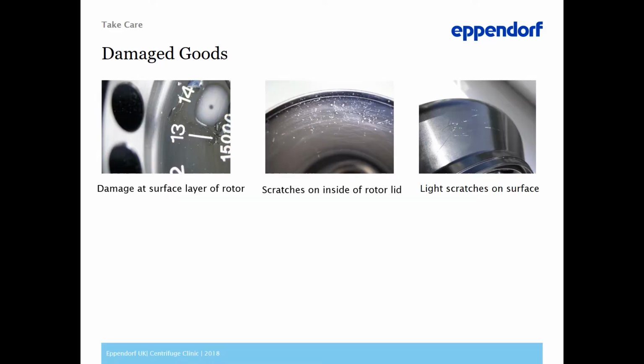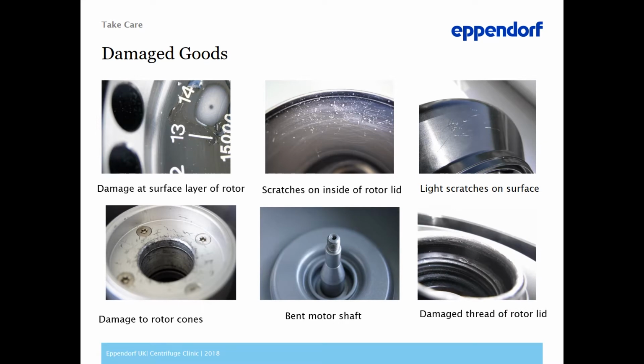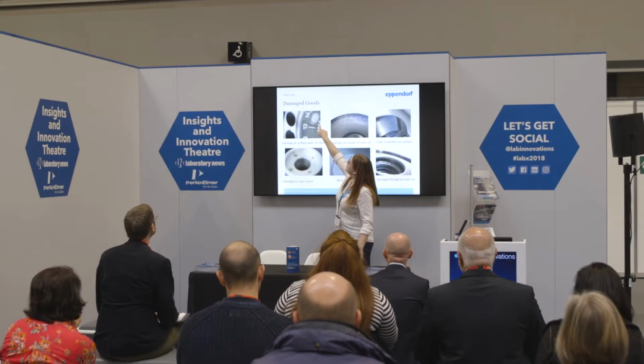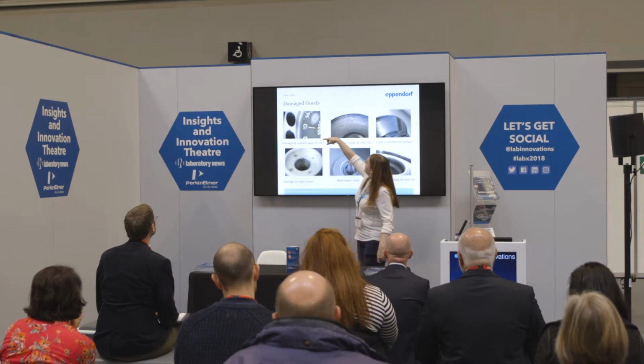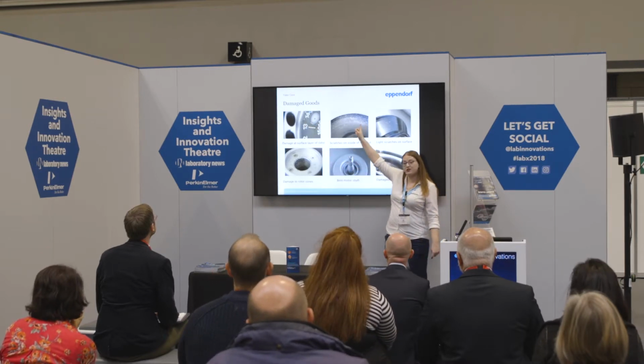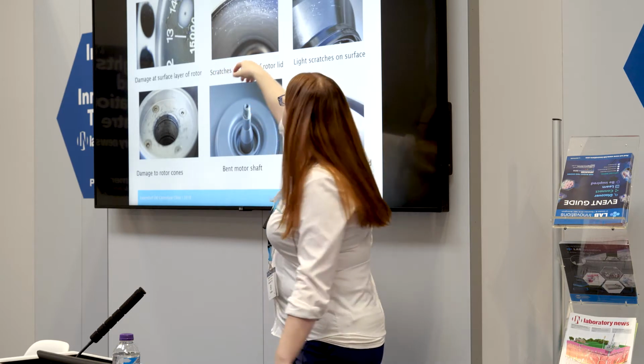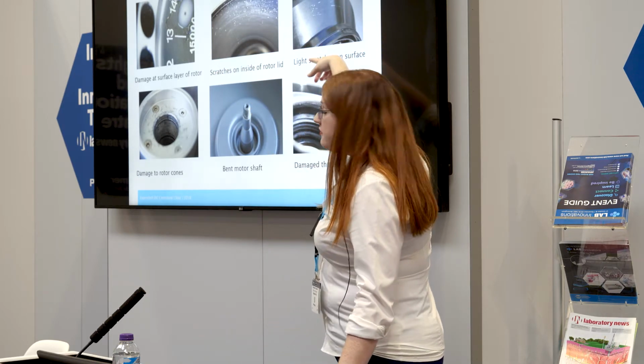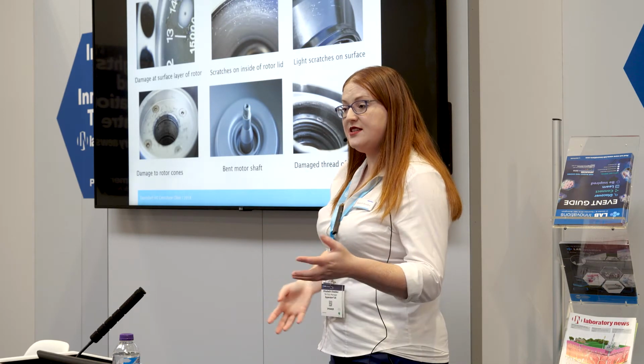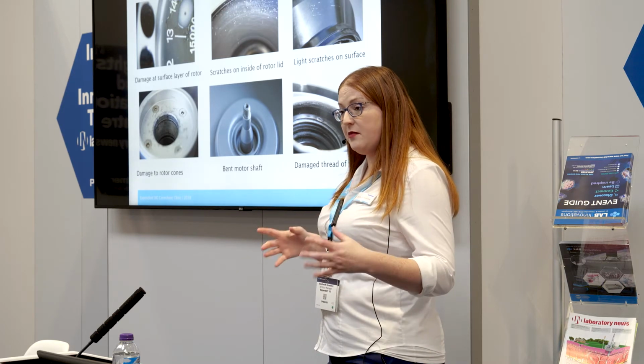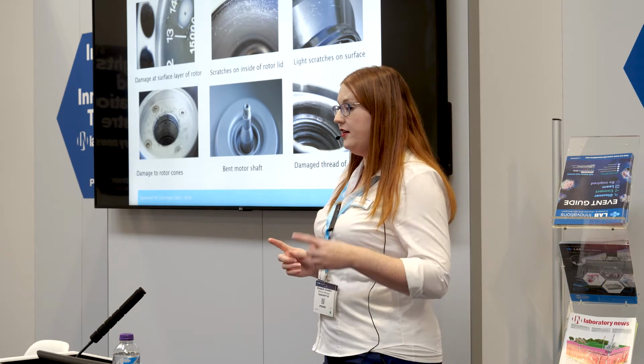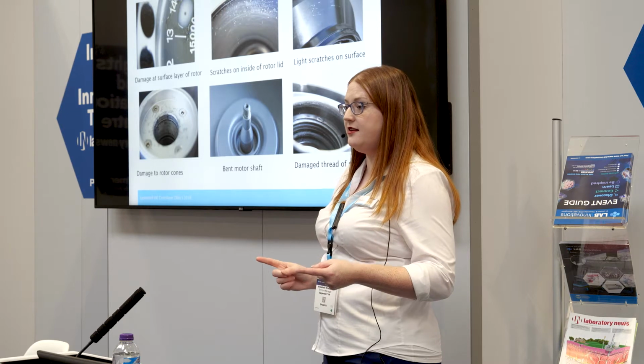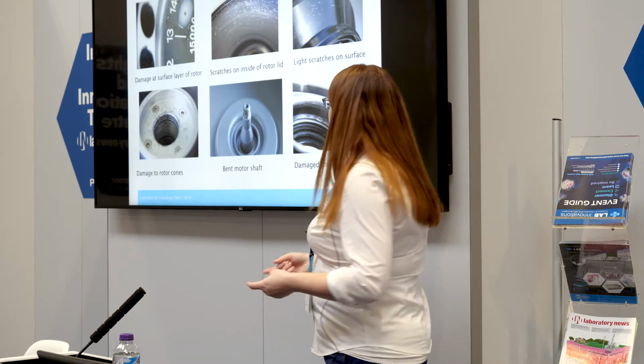So these are things to look out for. Most people can see the scratches and some corrosion around here. This is one of the most common issues: scratches on the inside of the rotor lid and scratches on the outside of the rotor. People don't think about scratches, but what that's doing is making it imbalanced. Unless you scratch it completely perfectly on exactly the opposite side of the rotor, it's not balanced anymore.